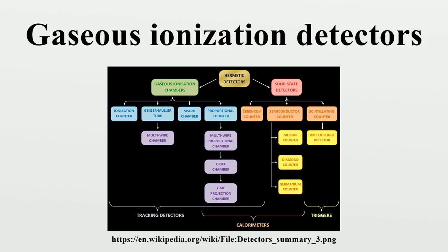Ionization chambers operate at a low electric field strength, selected such that no gas multiplication takes place. The ion current is generated by the creation of ion pairs, consisting of an ion and an electron. The ions drift to the cathode whilst electrons drift to the anode under the influence of the electric field. This current is independent of the applied voltage if the device is being operated in the ion chamber region.